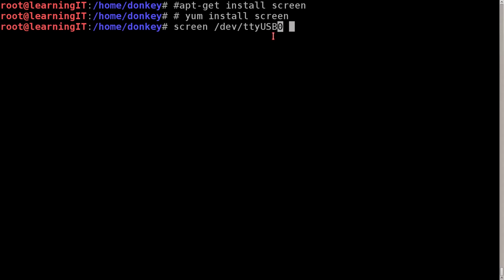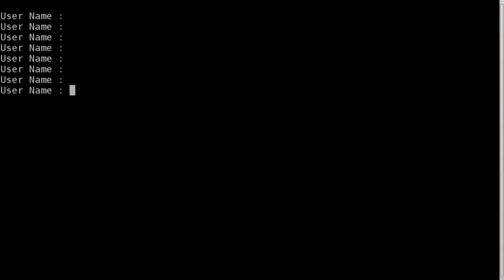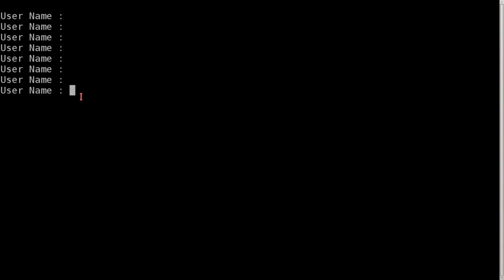So now if we hit the enter key, it actually opens up a new window. And when we push enter to initialize communication with the power distribution unit, it asks us for the username and password. If you're at this stage and can communicate with the unit, it means the serial connection works fine, and you're ready to initialize the reset procedure.